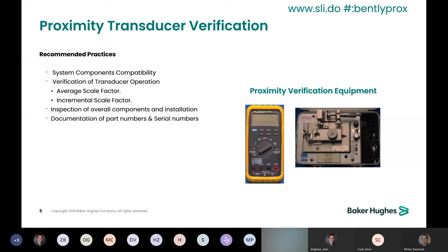Problems that can cause proximity probes to be out of tolerance include improper probe cable length, inadequate power supply voltage, crosstalk and side view conditions, inadequate target size, inappropriate target material, damaged components, or loose or dirty connections.